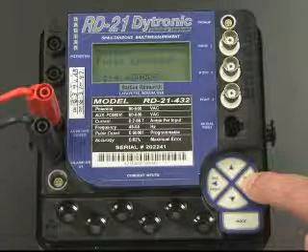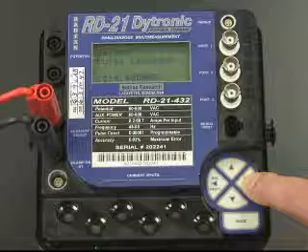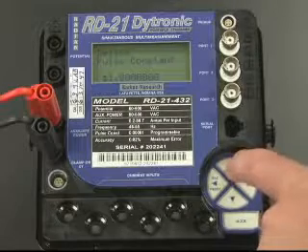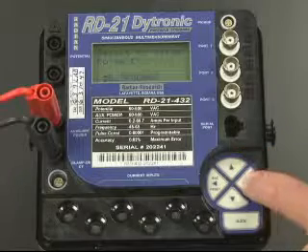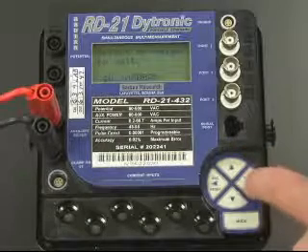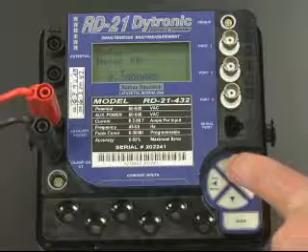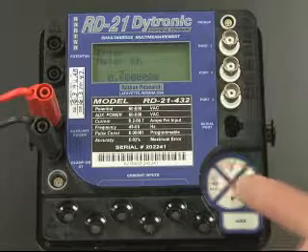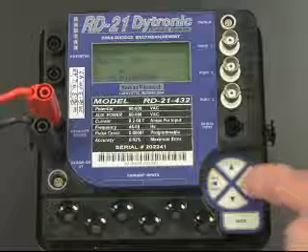If the correct K sub H is not available, scroll until the Edit option is displayed and press the Enter button. Use the left and right arrow buttons to select the digit of the K sub H and the up and down arrow buttons to select the correct value. Once the correct K sub H is displayed, scroll to the far right of the line to store the value for the test.